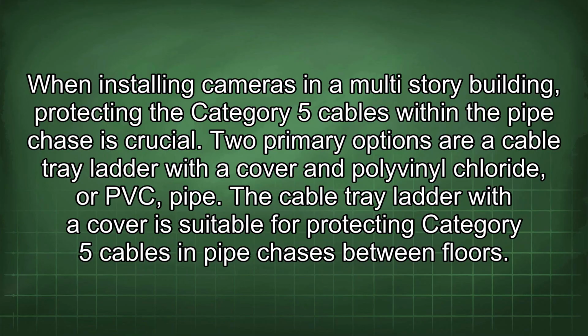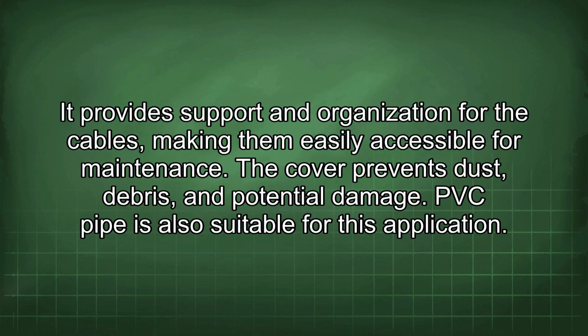When installing cameras in a multi-story building, protecting the Category 5 cables within the pipe chase is crucial. Two primary options are cable tray ladder with a cover and polyvinyl chloride, or PVC, pipe. The cable tray ladder with a cover is suitable for protecting Category 5 cables in pipe chases between floors. It provides support and organization for the cables, making them easily accessible for maintenance. The cover prevents dust, debris, and potential damage.